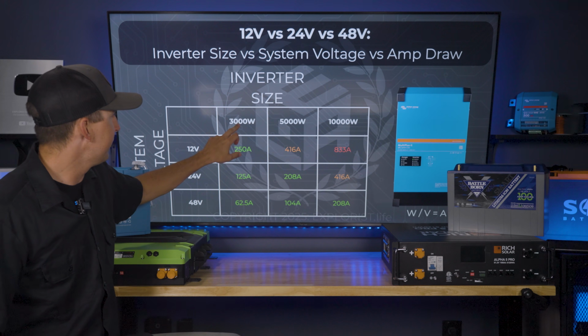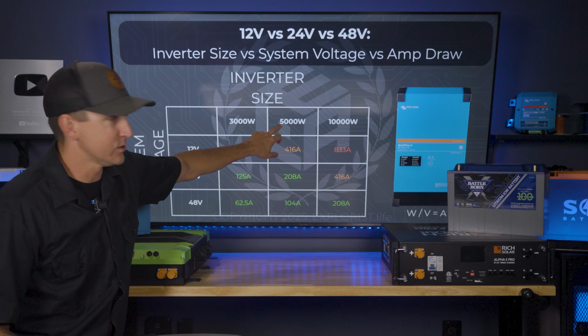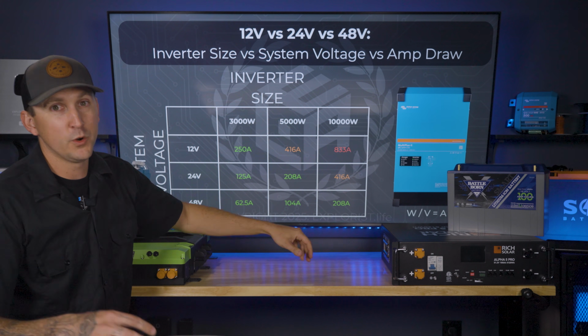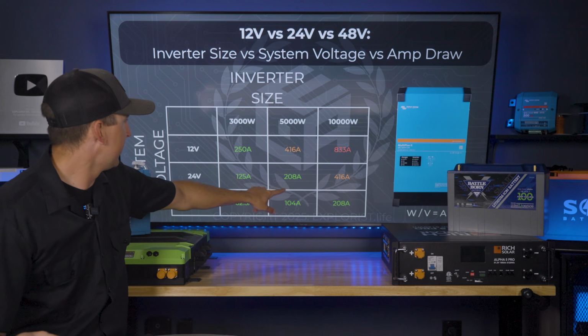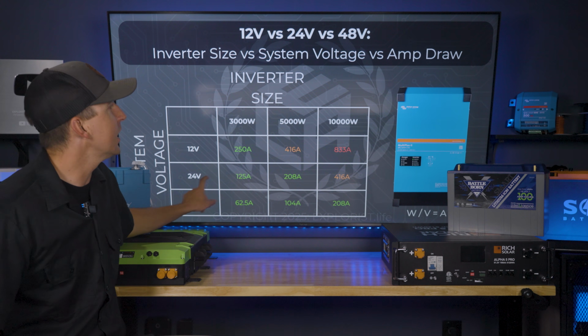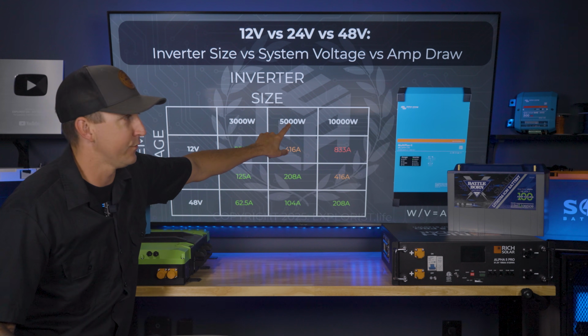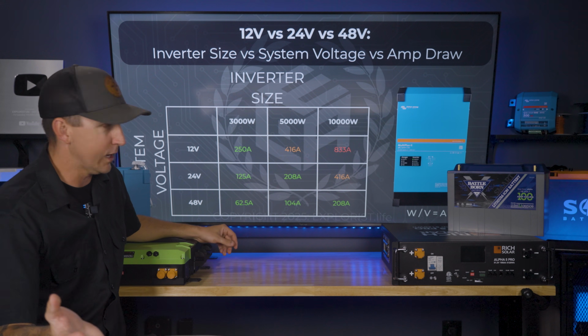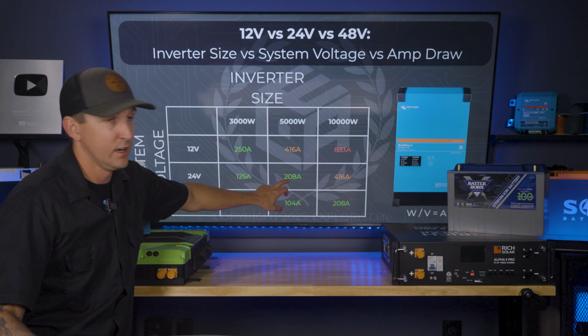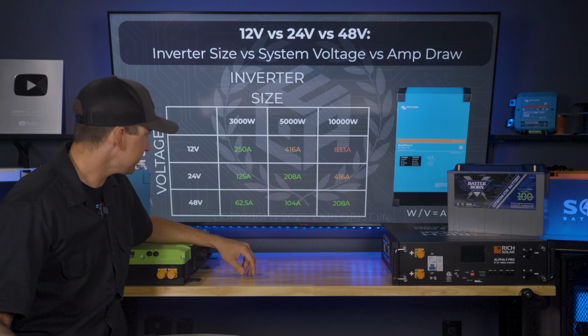So if you needed to be running a 5,000 watt inverter, that's where we really want to consider bumping to a 24 volt system. Get a 24 volt 5,000 watt inverter with a 24 volt battery bank. That way you're only pulling a little over 200 amps.